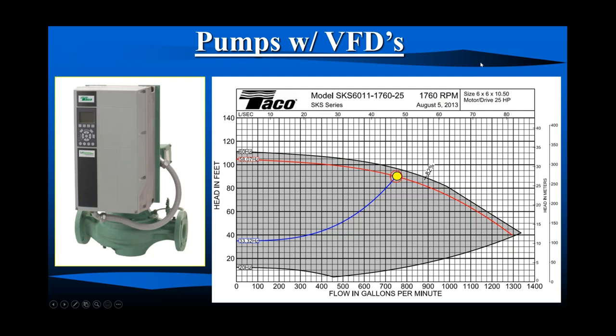Okay, good. So pumps with VFDs, right? We put a VFD on everything we possibly can, right? Pump affinity law number 3: halve the RPM and the horsepower decreases by 8 times. So VFDs on every pump. Most manufacturers are putting VFDs right on the pump, right? They map the performance points of the pump right into the VFD, because in the power calc there's flow, head, efficiency, and all that goes in there. And if you put all those points in there, this remembers the power required at all these points. And then you program it for design day and the control head.